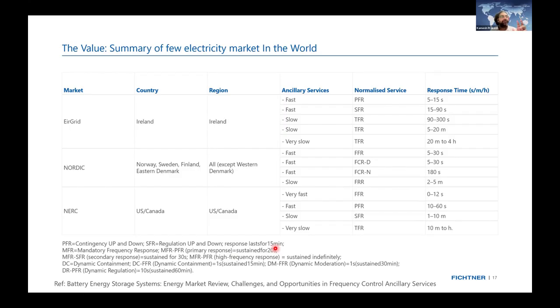Until 15 minutes, you know, in inverters we used to call LVRT and HVRT, low voltage ride through and high voltage ride through. Sometimes it might not be a fault. There might be an impulse, which your system will recognize as an impulse, and then it will be fine. But if it is recognized as a fault, then the corresponding isolators will open. So your system may not be truly stabilized unless you have the capability of LVRT and HVRT. These are the standards your inverters need to undergo, so that if they sense some disturbance, they can classify whether it is a fault or just a disturbance. Until then, my system will be requesting the response.